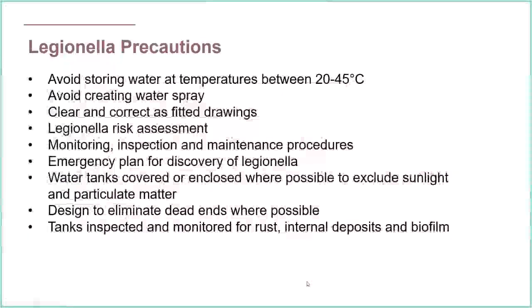So some precautions: avoid storing the water at a temperature between 20 and 45 degrees. I'd have thought that'd be fairly easy, but maybe your water storage tank is within a plant environment where lots of systems are running, generating heat, so the temperature could get a bit higher. Or maybe it's a residential system where you're storing it in the loft, so the water temperature could go higher. Ideally we want to store it above or below that range, but it's obviously a lot easier to do below than above.